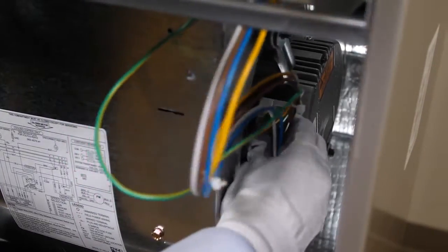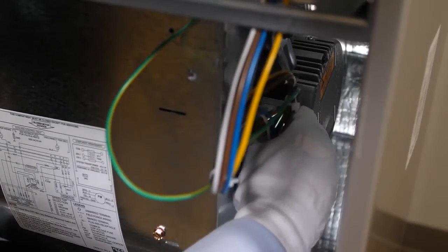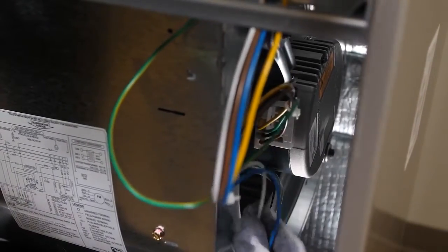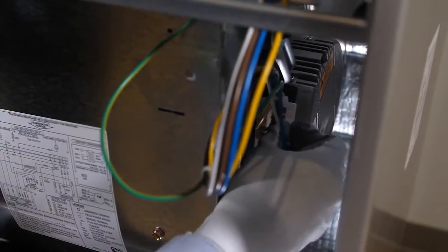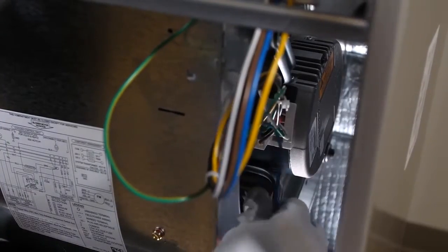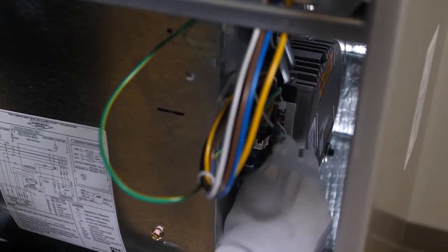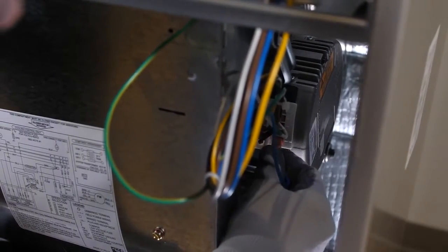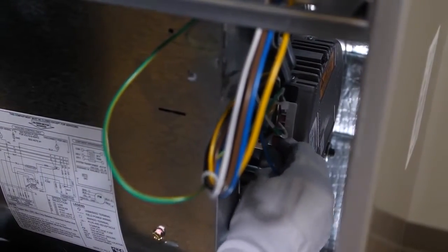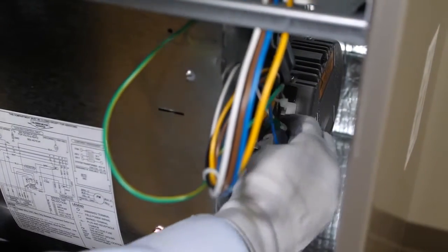Reconnect the power and signal connector housing and quick connect terminals to the original motor terminal locations. Make sure that the connector of the control is facing sideways or downward to prevent moisture from getting into the connector housing. Otherwise, the motor may have to be rotated. If you used tie wraps, check that they are holding the connector cables properly so that a proper drip loop is maintained.